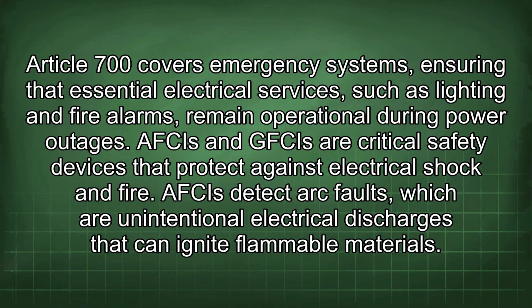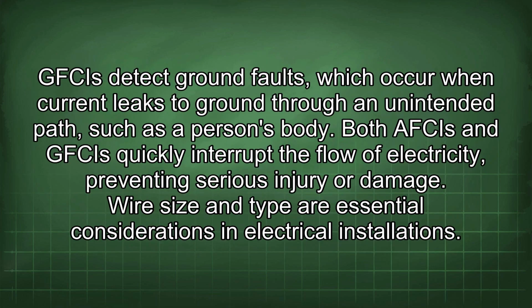AFCIs and GFCIs are critical safety devices that protect against electrical shock and fire. AFCIs detect arc faults, which are unintentional electrical discharges that can ignite flammable materials. GFCIs detect ground faults, which occur when current leaks to ground through an unintended path, such as a person's body. Both AFCIs and GFCIs interrupt the flow of electricity, preventing serious injury or damage.